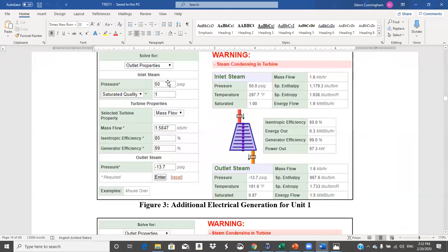This is the low pressure turbine, so it's going to see 50 PSIG. And basically we're saying it's saturated. Here's the mass flow that we're going to pick up. That's in 1,000 pounds, so that's 1,585 pounds mass an hour. You have to dig out the isentropic efficiency, and then the generator efficiency it's going to convert to electricity. This was the condenser pressure. So you see we're at a vacuum, which is typical. And then you enter, and it gives you the performance out of this thing.